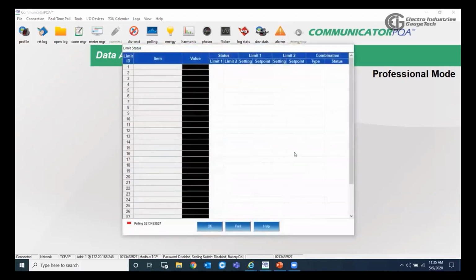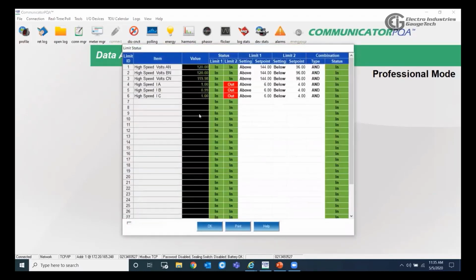And we also have the alarms. This is based on how we set the alarm on the profile. For example, this meter has the voltage set so that it alarms if it's above 144 and below 96. So you can see that the voltage is always 120, so it's within the limit. That's why we have the green here. While the current here is set for above 6 and below 4. So you can see that limit 2 is hit, and that's why we got red.